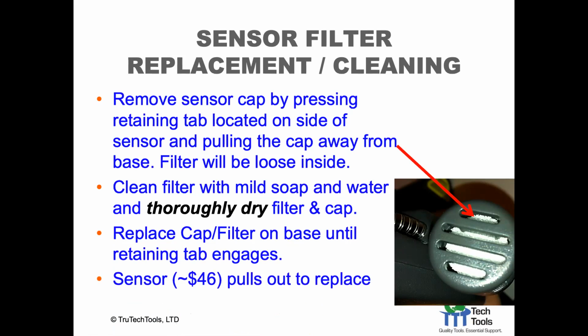And the sensor is about $46, and it's also inside there. It's keyed. It has, I believe, 4 little legs on it. It has a tab which keys it. You just have to make sure you put it in the correct orientation, because those are actually leads and they mean something to the unit to be installed correctly.